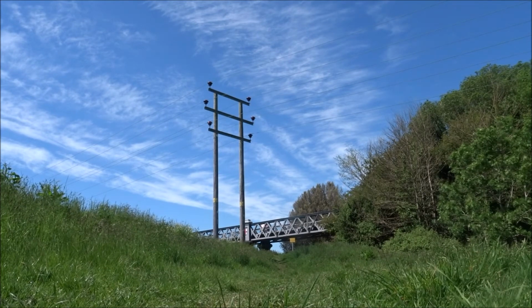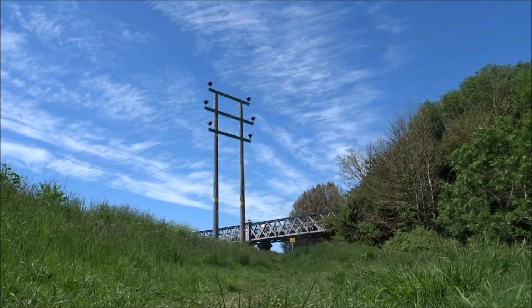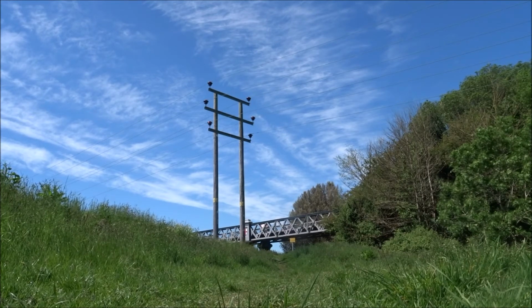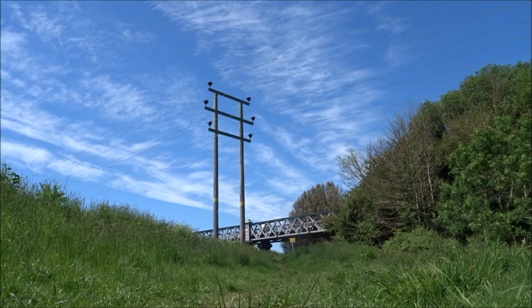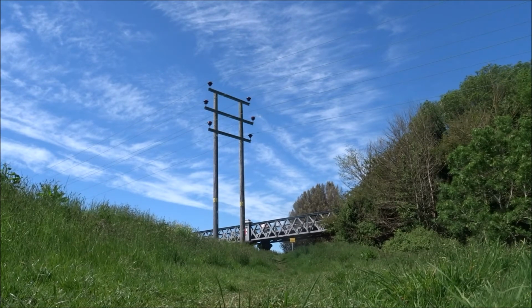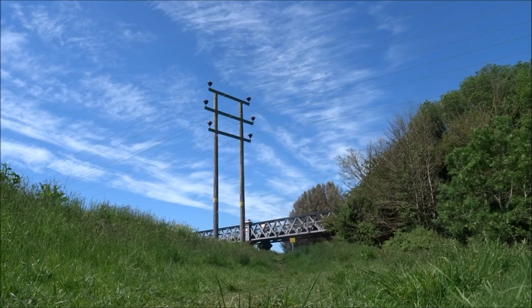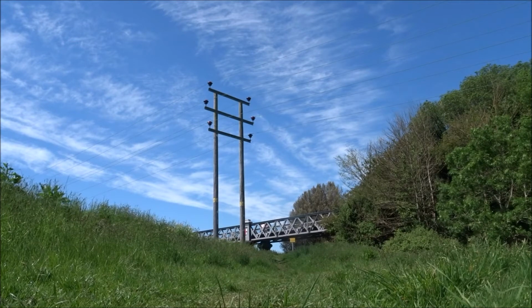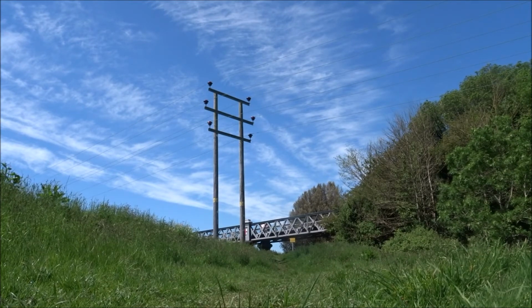So you need to call 999 and get the local power company to isolate the transformer or the line where that injured party is. Energized power lines will energize equipment such as HIABs on cranes, and once it arcs to ground, you will have an energized area of ground, which is a danger zone, and you need to be very careful.